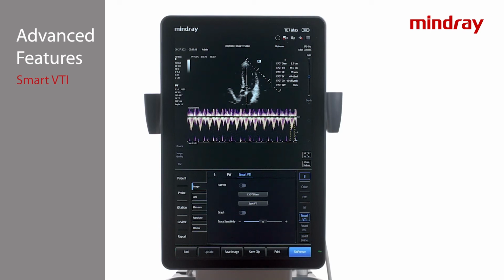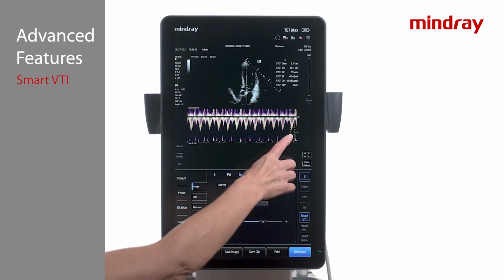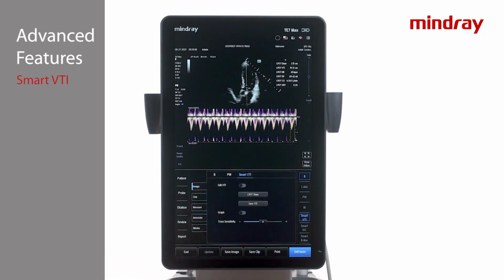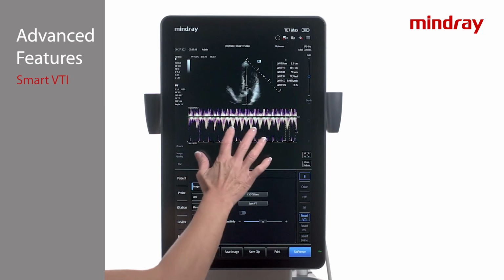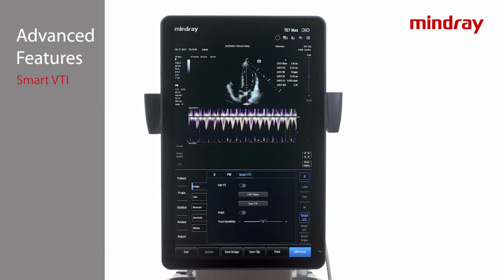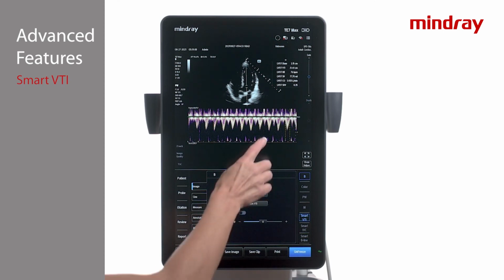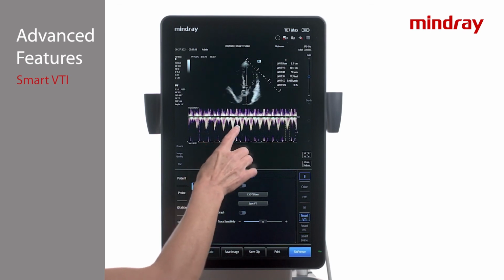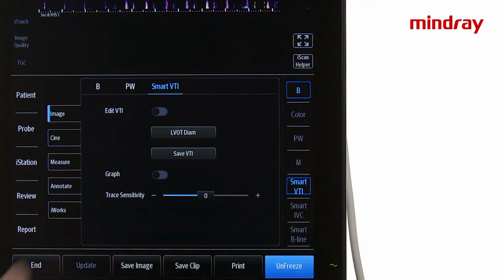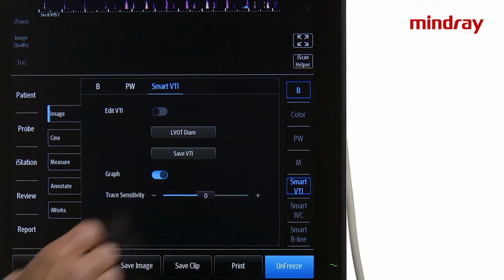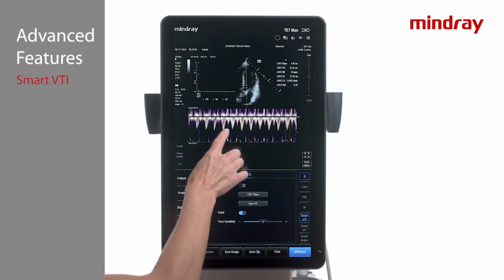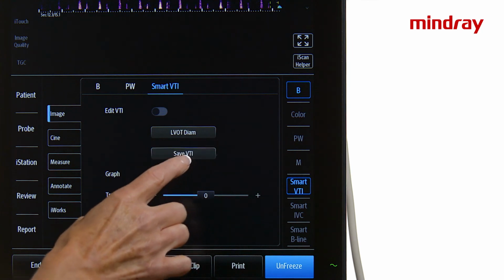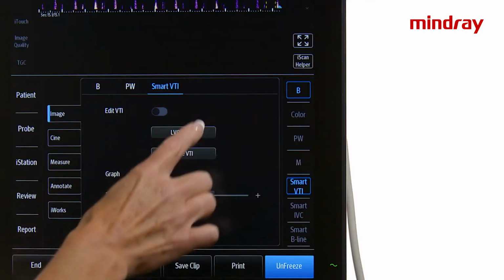The Doppler envelope being used for the displayed data is the last one to the right. It is indicated with dotted lines. Scroll to a different complex if this one is suboptimal, or manually adjust the trace with the Edit VTI tab using the caliper tool. Data will change as soon as a different complex is chosen or there is a change to the tracing contour. By turning on the graph and tapping Save VTI, the system can plot multiple data points for the patient. The data from Smart VTI can be found in the Fluid Management Report type.